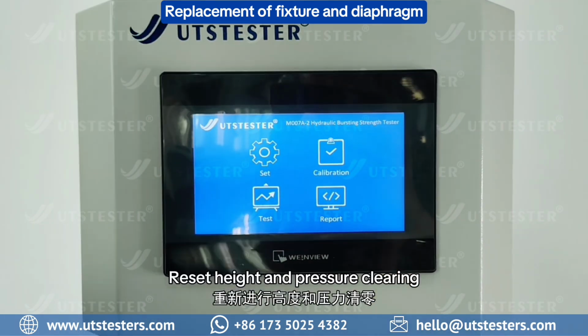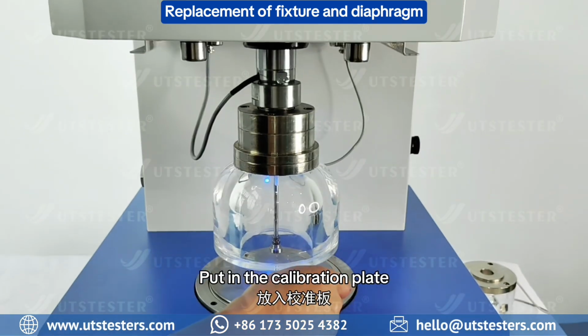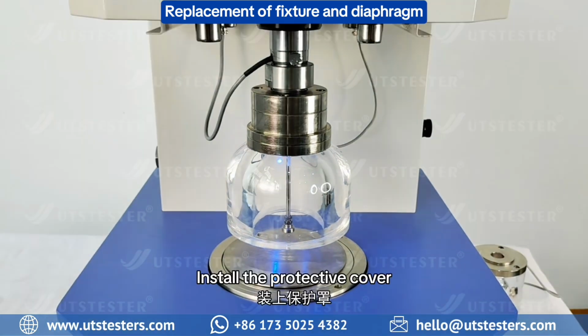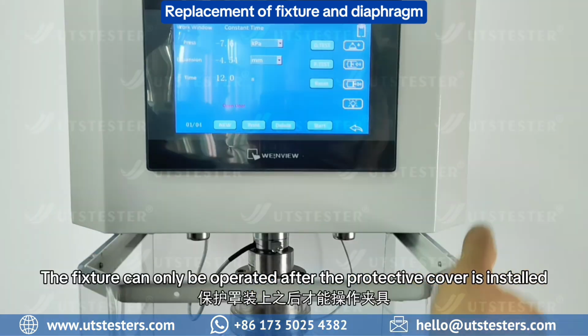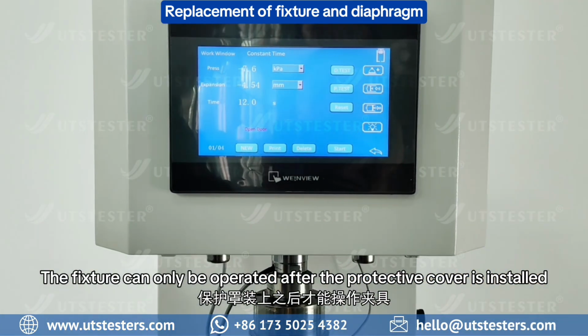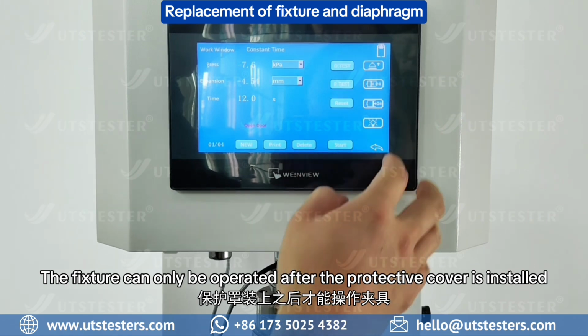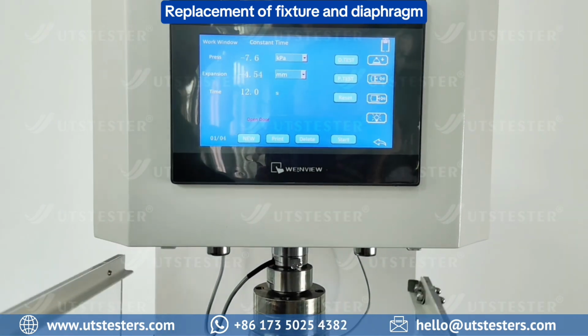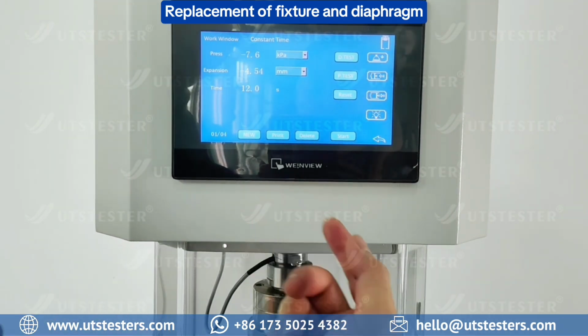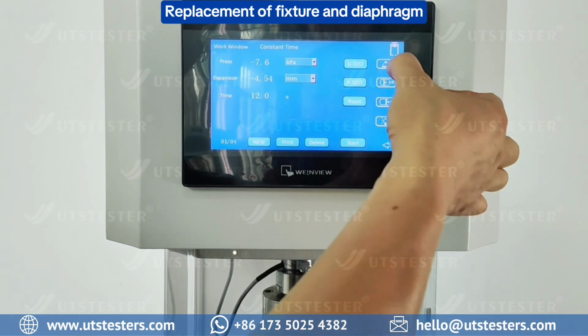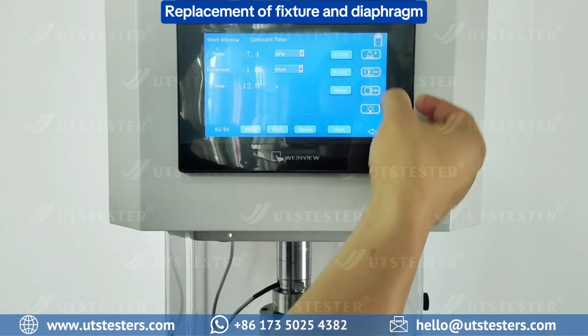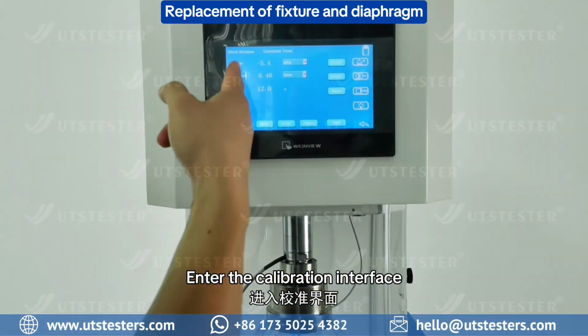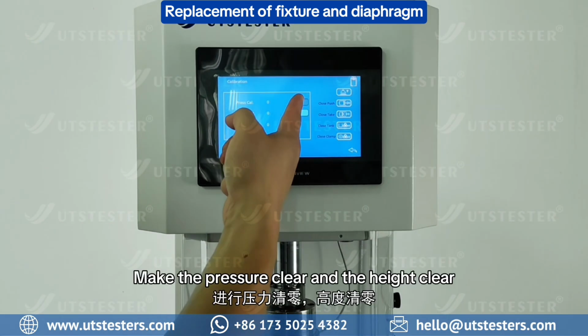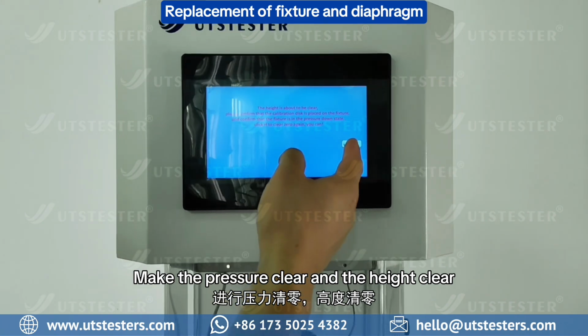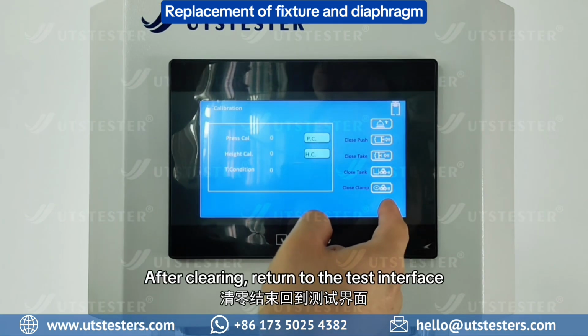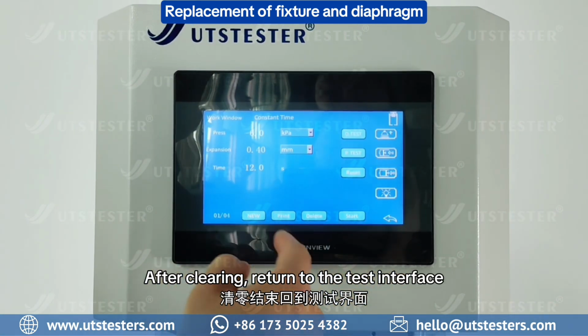Reset height and pressure clearing. Put in the calibration plate. Install the protective cover. The fixture can only be operated after the protective cover is installed. Press down the fixture. Enter the calibration interface. Clear the pressure and clear the height. After clearing, return to the test interface.